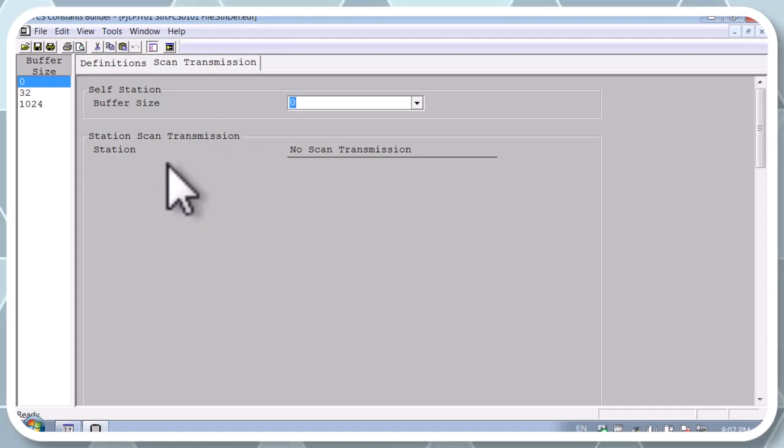And my friends, the global switch, which we used in some of our programs, is an internal Boolean on-off signal that can be shared with all FCS in the same domain. If one FCS changes the switch, all other FCS receive the updated value. And the update happens, as I remember, every 100 milliseconds.